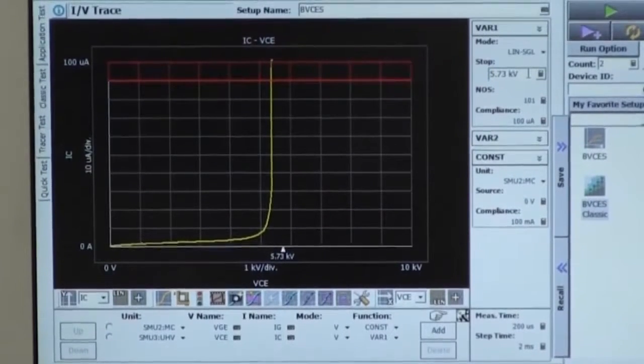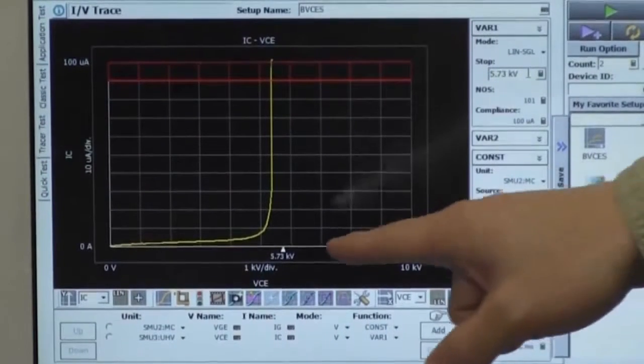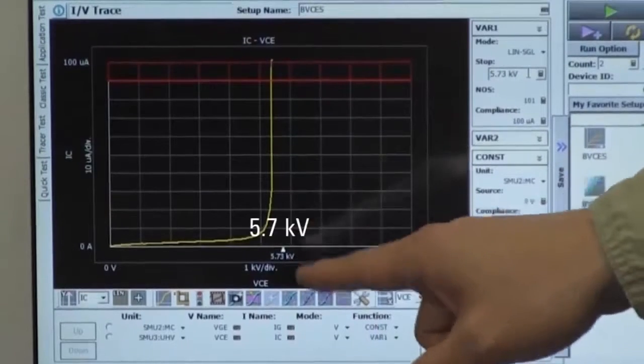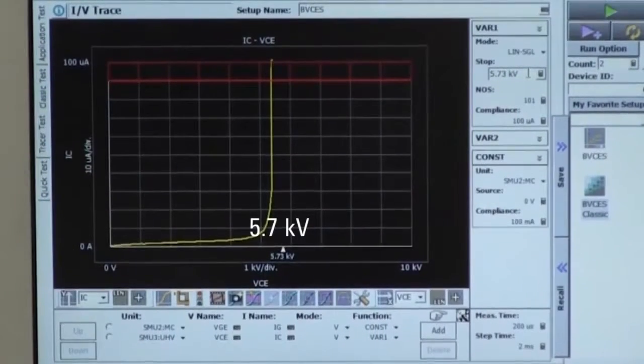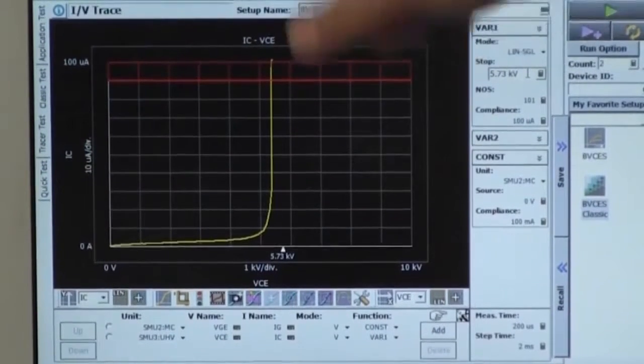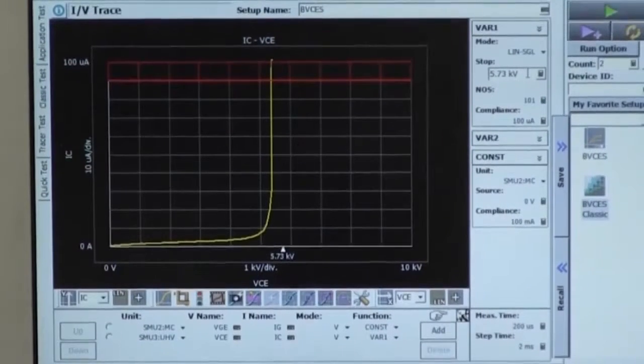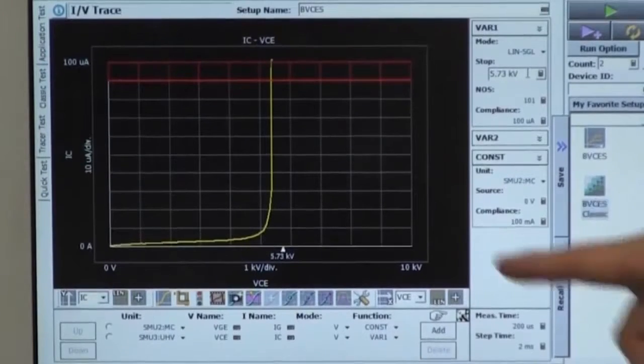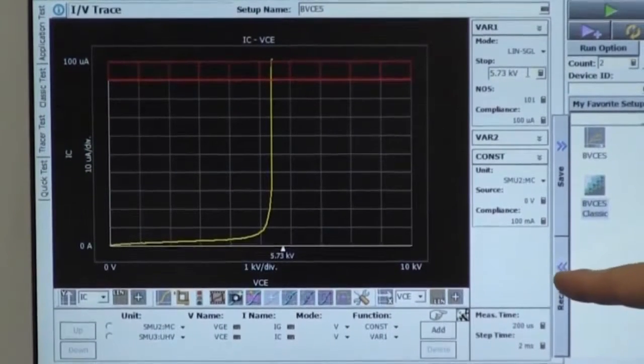Okay, so device is broken around 5.7 kV. Of course, you can read out the breakdown voltage from this tracer test mode graph. But B1505A has a unique function to extract breakdown voltage automatically.